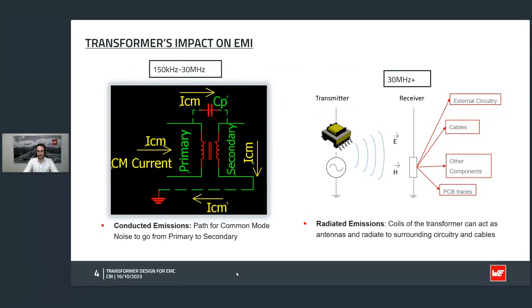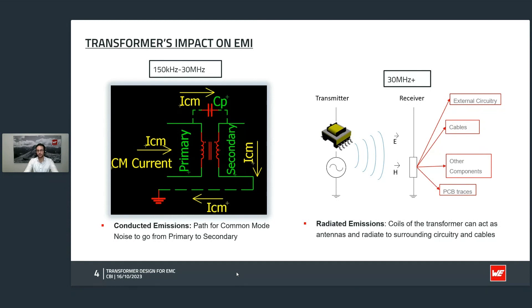We distinguish between conducted emission and radiated emission. Conducted emission is always transmitted by the electric path. We talk here about an isolated transformer where primary and secondary are electrically not connected — they are only connected by the magnetic core and also by the interwinding capacitance. If we apply a higher frequency signal, the impedance of the capacitor goes down and it becomes conducting. So the noise that we inject into the transformer can pass through the interwinding capacitance. It is therefore a main target to reduce the interwinding capacitance if we want to improve the EMI behavior of the transformer.